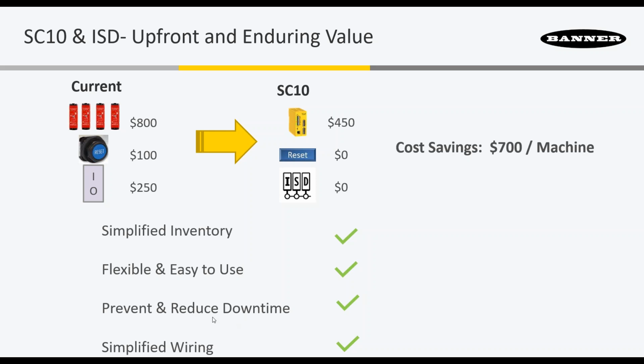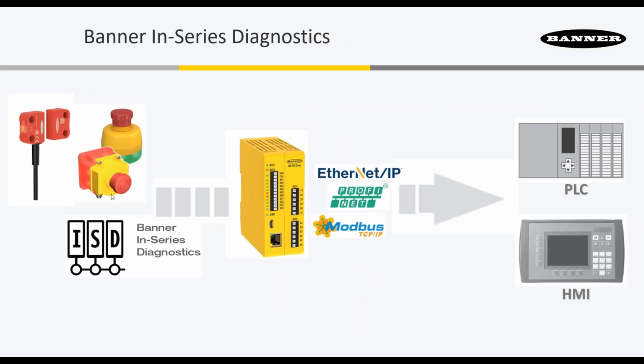And the other thing we're going to do, so on the HMI before, they could reduce downtime by identifying what device caused the machine to shut down. We'll be able to prevent downtime with in-series diagnostics to be able to alert you when there's an issue with the system before it shuts down. I'll show you more on what that means. So what we're doing here with in-series diagnostics is we have devices that have this protocol built into them, and they send their device information to the SC10, which then goes over these protocols to the PLC and the HMI. So you're getting sensor level information directly on the PLC and the HMI over Ethernet IP, Profinet, and Modbus.